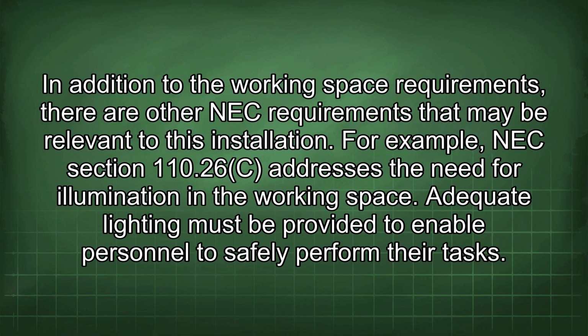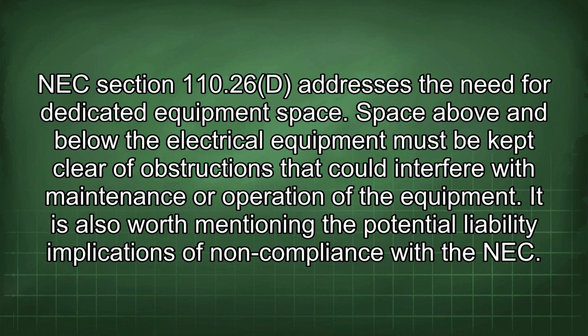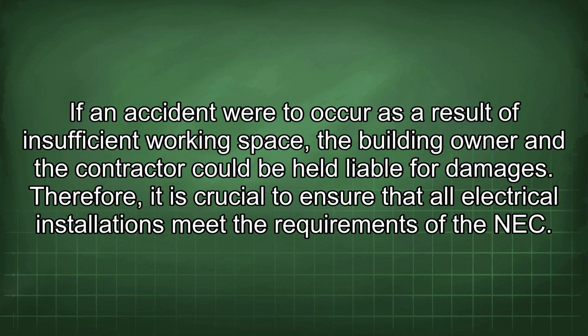In addition to the working space requirements, there are other NEC requirements that may be relevant to this installation. For example, NEC section 110.26(C) addresses the need for illumination in the working space. Adequate lighting must be provided to enable personnel to safely perform their tasks. NEC section 110.26(D) addresses the need for dedicated equipment space. Space above and below the electrical equipment must be kept clear of obstructions that could interfere with maintenance or operation of the equipment. It is also worth mentioning the potential liability implications of non-compliance with the NEC. If an accident were to occur as a result of insufficient working space, the building owner and the contractor could be held liable for damages. Therefore, it is crucial to ensure that all electrical installations meet the requirements of the NEC.